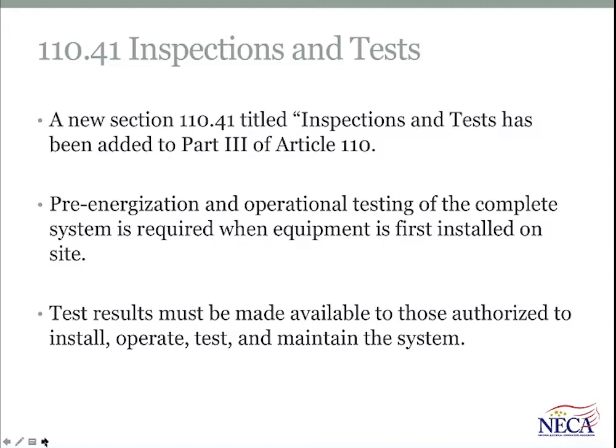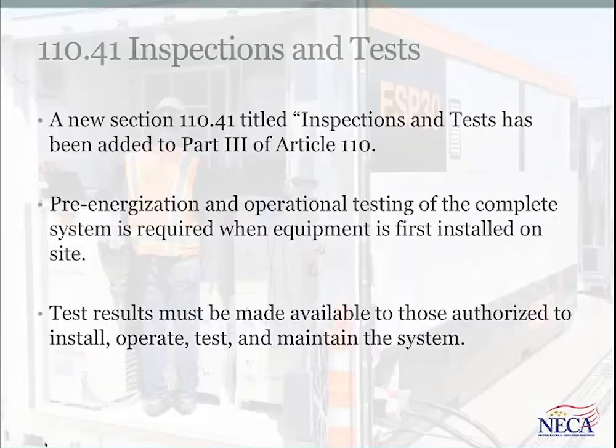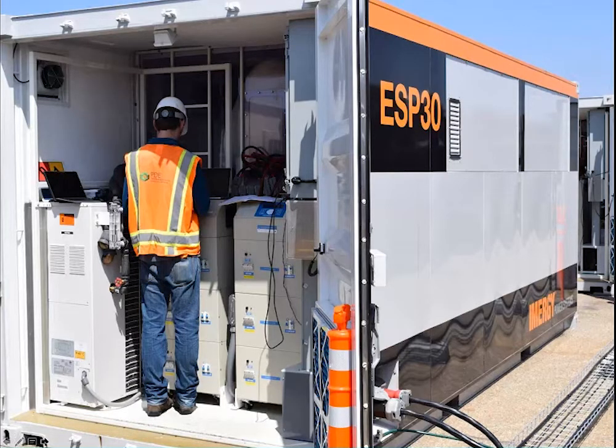The NECA documents talk about the pre-energization tests and so forth, but now it becomes a requirement in the NEC. And by having it in Chapter 1, it doesn't matter if they're inside or outside feeders or branch circuits in the medium and high voltage range. They have to have the operational testing and the pre-energization testing and associated documentation that can be used for authorizing the equipment to be energized. Oftentimes, inspection authorities will require that documentation as a basis for their approval and release to allow it to be energized. Photo is an example of some equipment that is undergoing some tests.